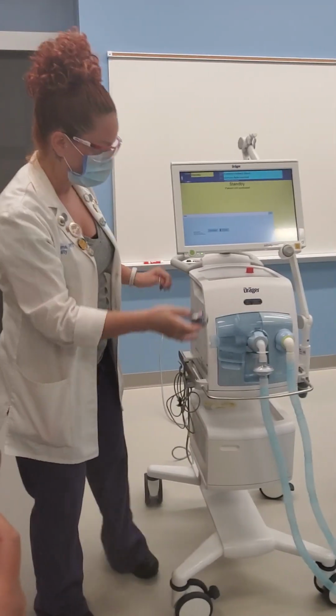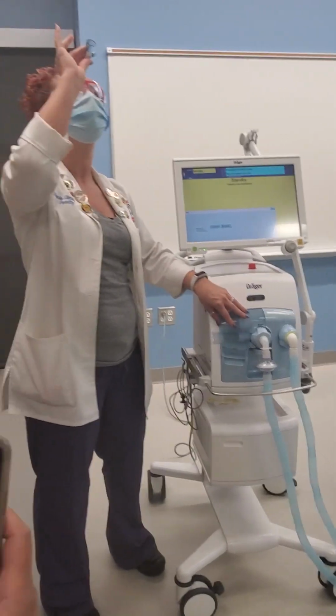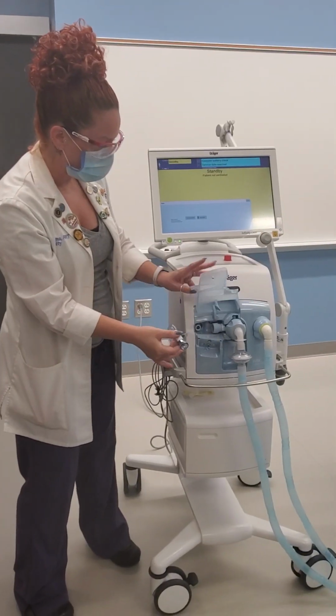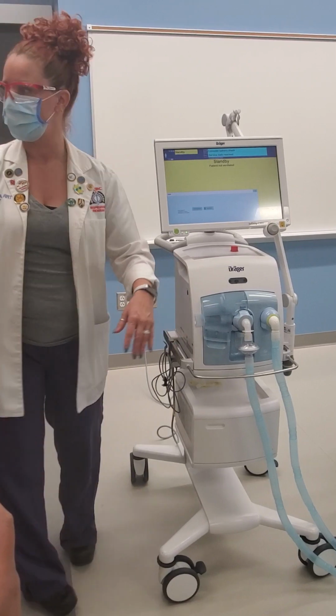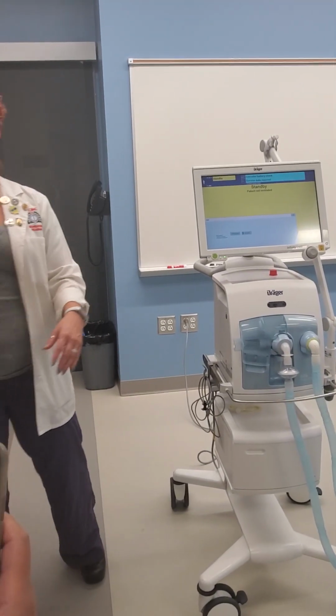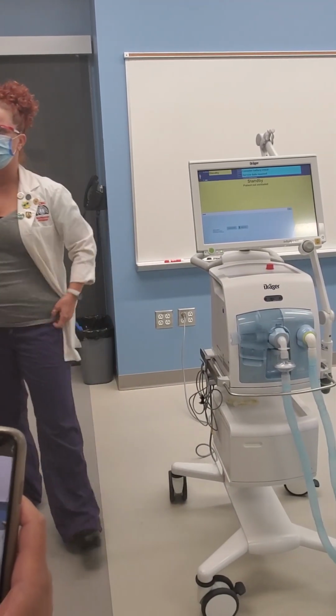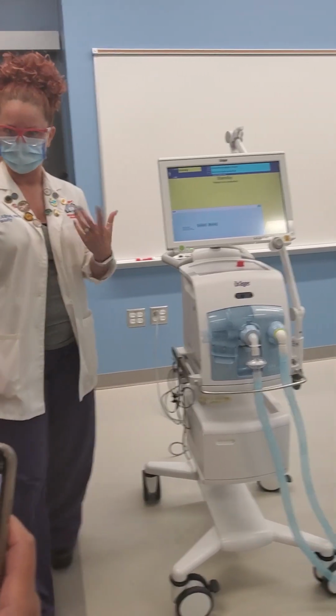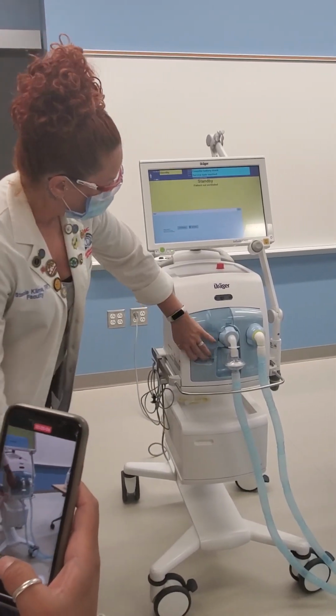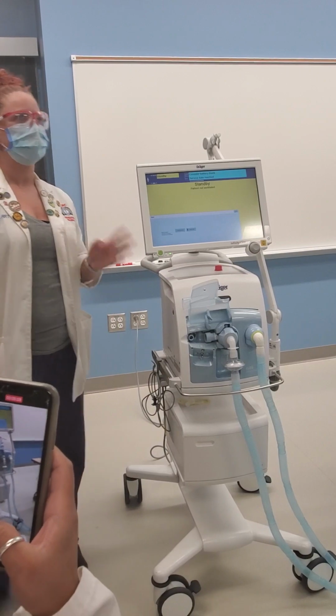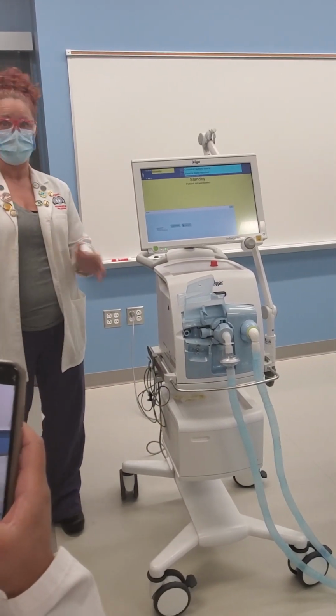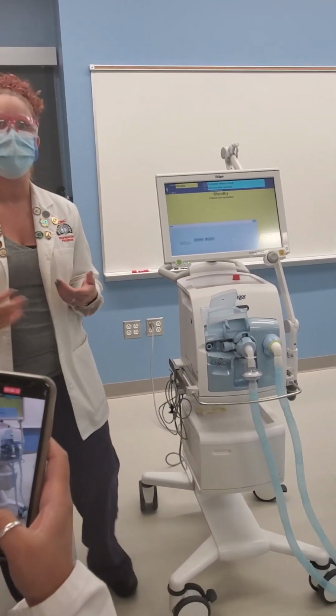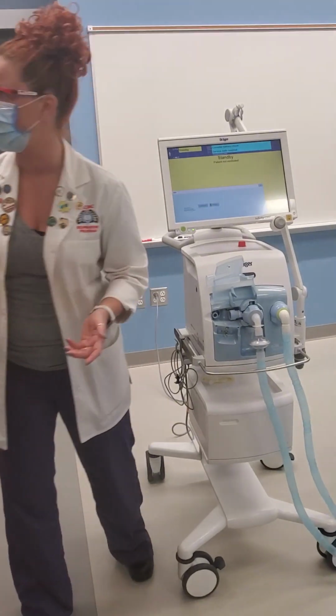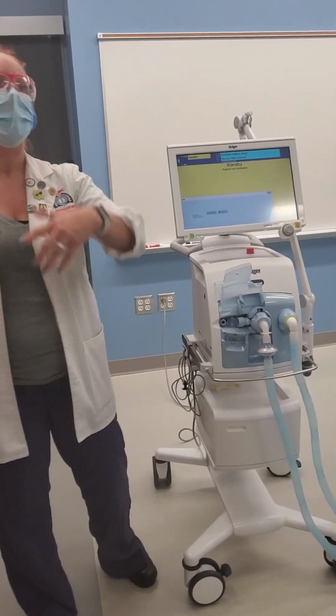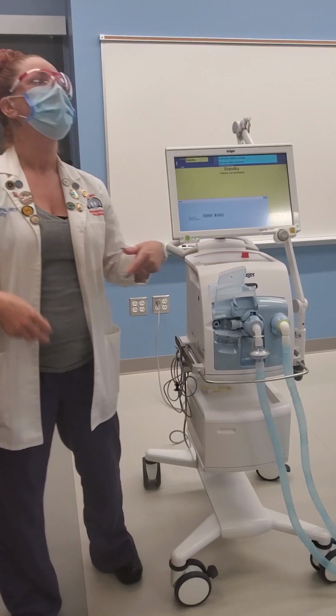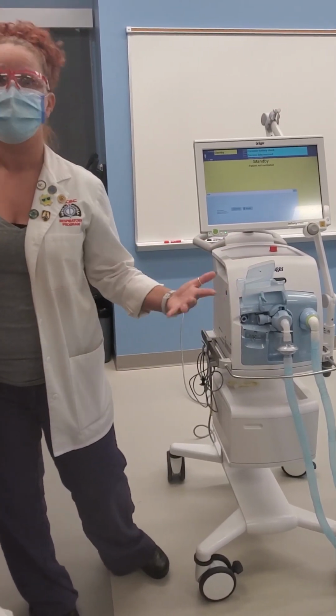So you would take out your flow sensor, make sure the filament is intact, put it back in and calibrate the flow sensor. I'm gonna actually pass it around. So if you wanna take a look at the filament, do it with a sense of urgency so we can keep moving. And I'll show you how to put that back in. Most of the time, if you take it out, put it back in, and the filament is still attached and you calibrate the flow sensor, that will rectify the situation. Okay? And you'll see your values come up, all is well in the world.